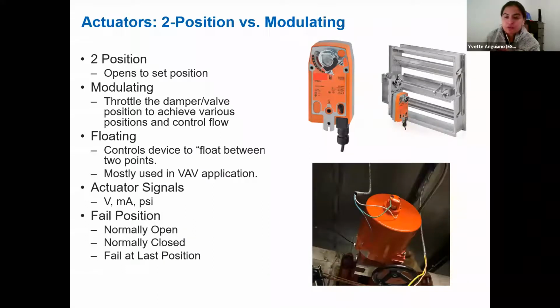You'd want to fail your damper or valve open when there's a safety issue as a concern. So for example, in an air handling unit situation, you'd want to prevent your coils from freezing, so you'd fail those outdoor dampers closed. Or for example, in the supply duct of that same air handling unit, you'd want to fail your dampers open so that there's no overpressurization of the duct. And then lastly, you'd want to fail in last position when there's not a concern for safety, such as in a terminal unit, such as a VAV damper.